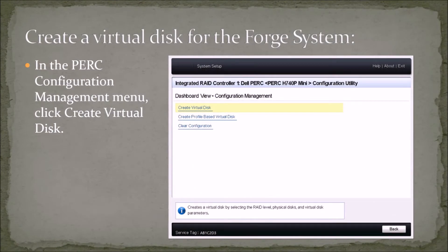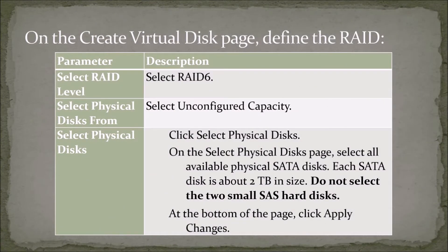Create a virtual disk for the Forge system. In the PERC configuration management menu, click Create Virtual Disk. On the Create Virtual Disk page, define the RAID level — select RAID 6. Select physical disks from unconfigured capacity. To select physical disks, click Select Physical Disks. On the Select Physical Disks page, select all available physical SATA disks. Each SATA disk is about 2 TB in size.